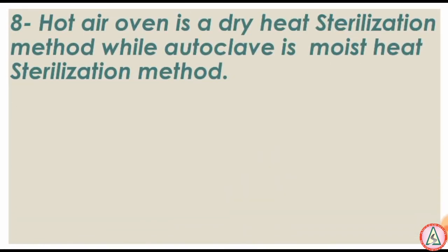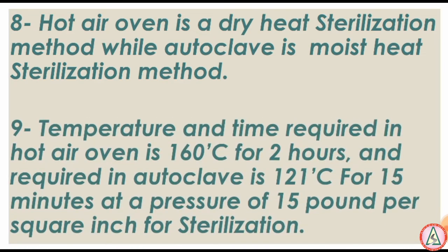Hot air oven is a dry heat sterilization method, while autoclave is a moist heat sterilization method. The temperature and time required in a hot air oven is 160 degrees centigrade for two hours. For autoclave, it is 121 degrees centigrade for 15 minutes at a pressure of 15 pounds per square inch.